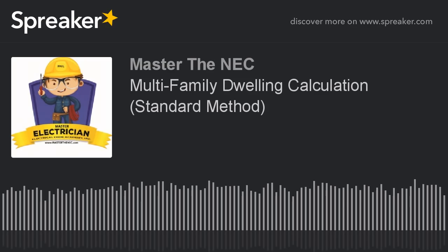I teach you everything that you ever want to know about that in that video. So I encourage you to go watch that video. It doesn't cost anything. It's free. It's a good video, and it teaches you everything you need to know there. So you size your conductors based on the need for 1200 amperes because you're going to have it terminated into a 1200 amp overcurrent protective device.